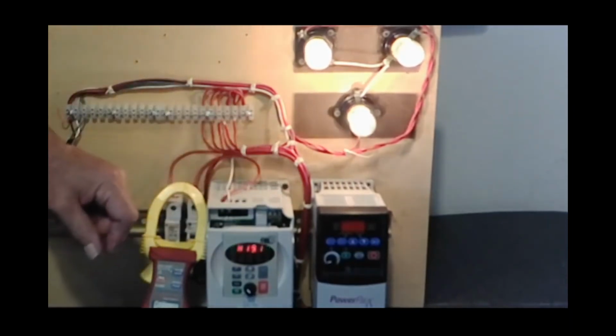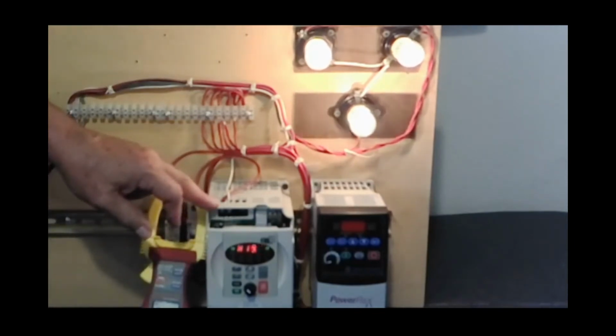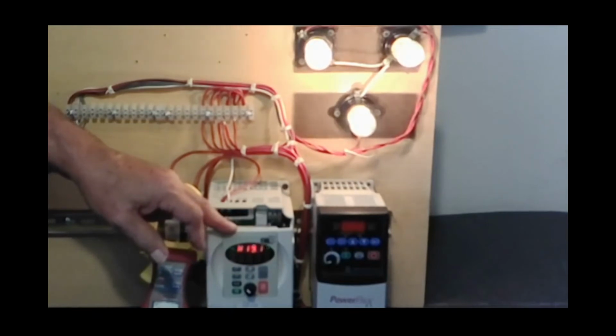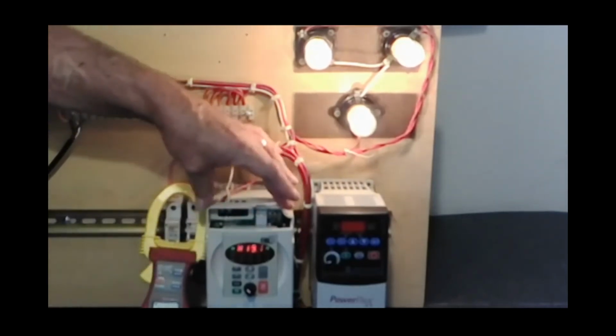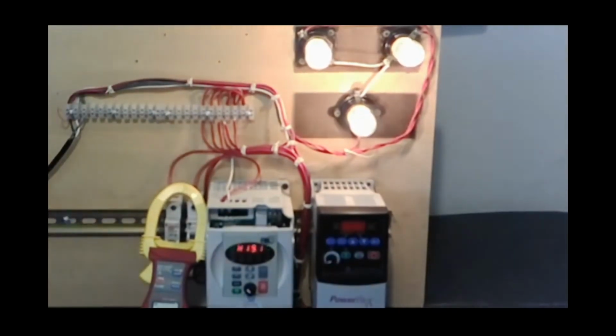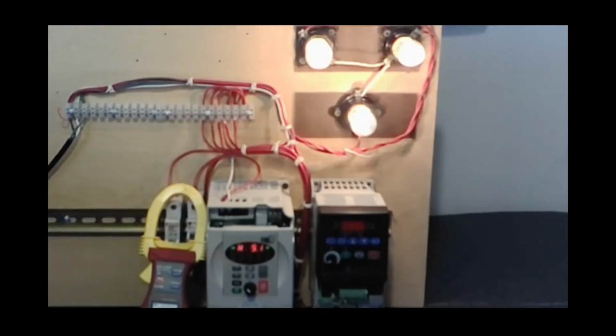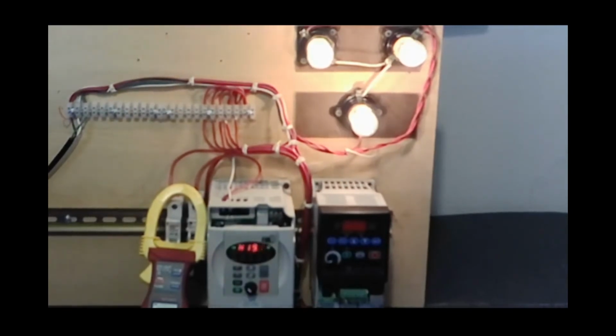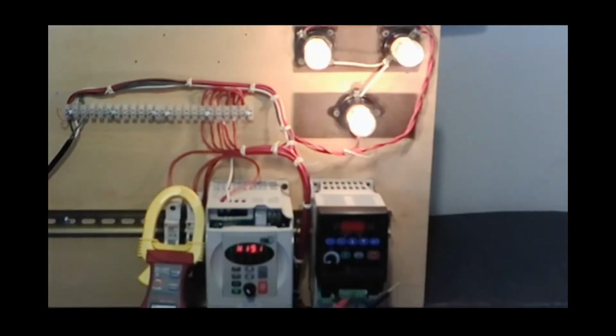Well, the power problems are one thing. That's easy to identify. But now the next question is, how is this drive operating? This drive might be getting a signal from a PLC, a building automation, or another drive. It could be getting a signal to start or run from another location. If that be the case, then the signals that go in and out could be something completely different. There's going to be terminal strips for these types of connections. And again, it doesn't matter which drive it is, you're going to need some type of manual to identify which terminals are which. A lot of times these terminals have to be jumpered out, and that would complete the circuit to allow the drive to run. But then again, I can take this jumper out and replace it with a PLC input. I can replace it with building automation. There are terminals here where I can set a speed limit for the drive.